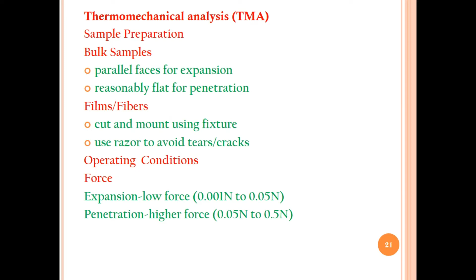Operating conditions are also important in TMA. For example, force is most important. For expansion, low force. If we want to analyze the expansion behavior of the sample under observation in TMA, then we have to apply a low force. It must be 0.001 Newton to 0.05 Newton. Then for penetration, a high force. For the penetration type of measurement that we already discussed with the former probes, if we have a penetration type of probe, then we have to apply a high force. The force must be in the range of 0.05 Newton to 0.5 Newtons.